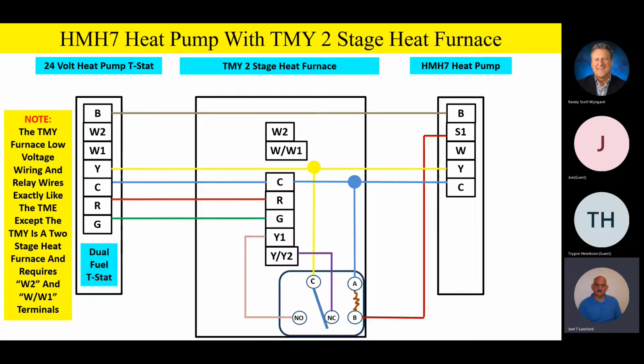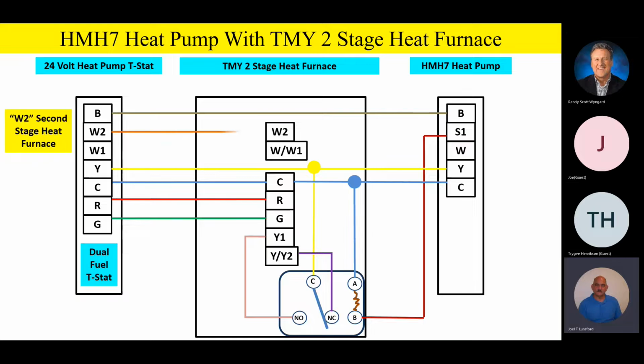B goes to B. However, because the TMY is a 2-stage furnace, a 2-stage heating product, it's also 2-stage cooling, just like you can see on the schematic. But because it's a 2-stage heating product, we're going to take W2 from the thermostat and hook it up to W2 on the furnace. And then W1 from the thermostat will go to that W/W1 terminal and take it outside. So the only difference between the TMY and the TME is the fact that we have another terminal for this 2-stage furnace. Does that make sense to everybody?